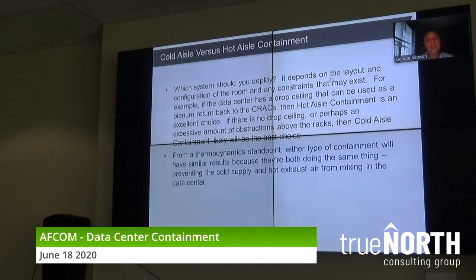Because again, you're doing the same thing. You're separating your cold supply air from your hot exhaust air. You're able to raise your temperatures, very similar. You're able to either turn off CRAC units or lower fan speeds. You're going to have very similar results.